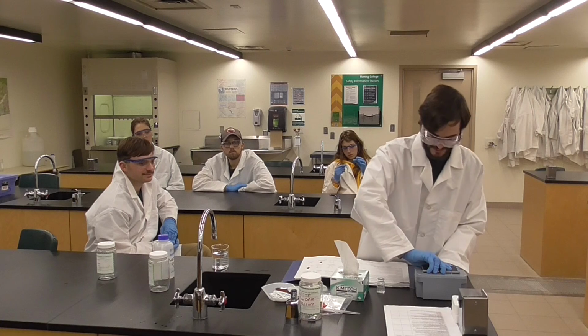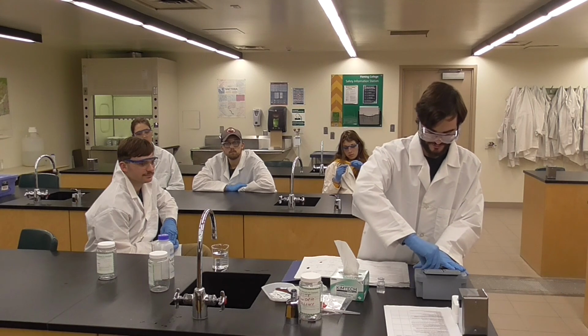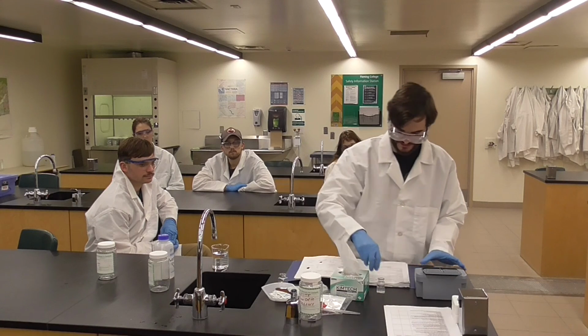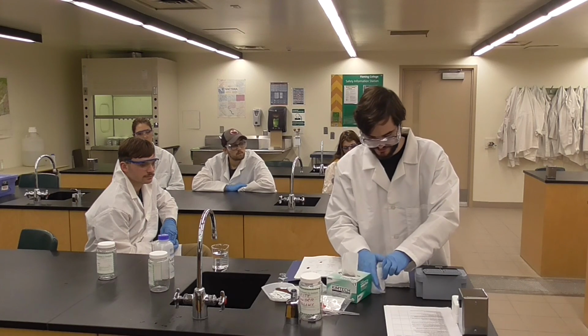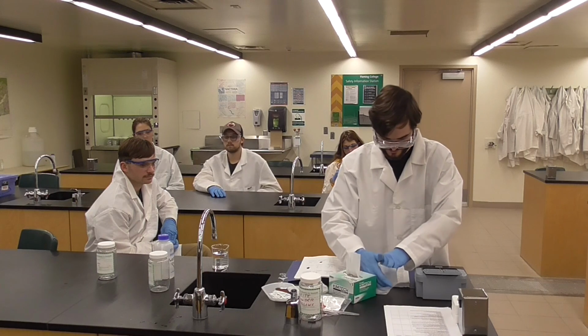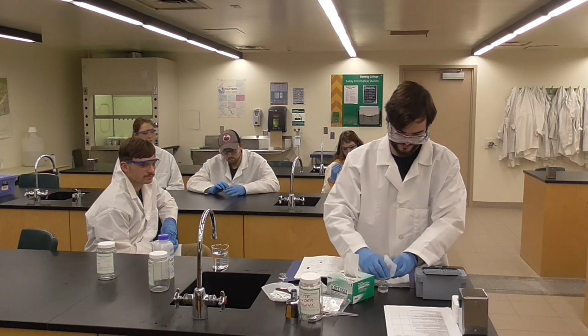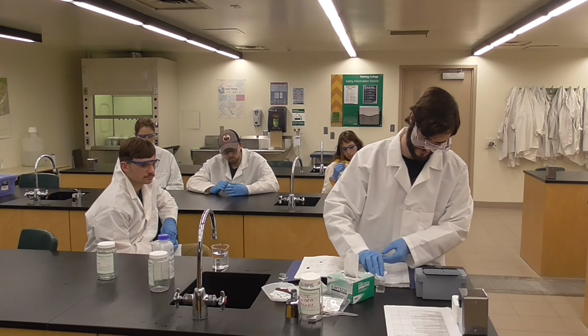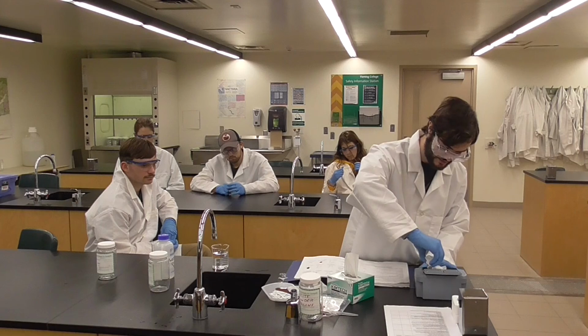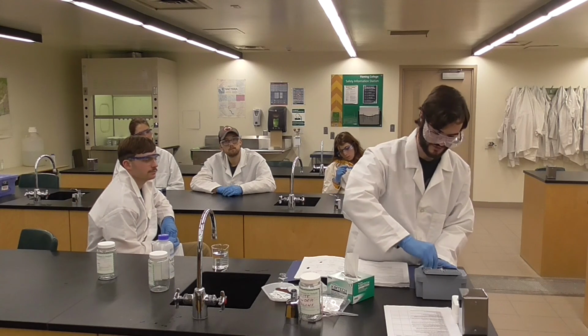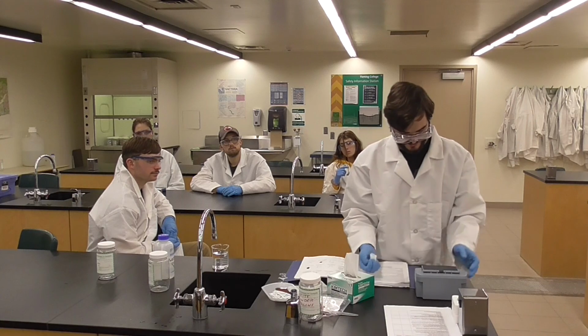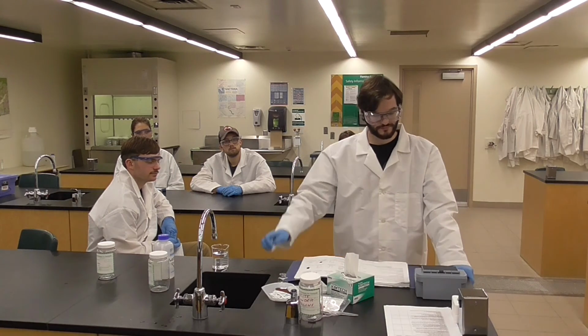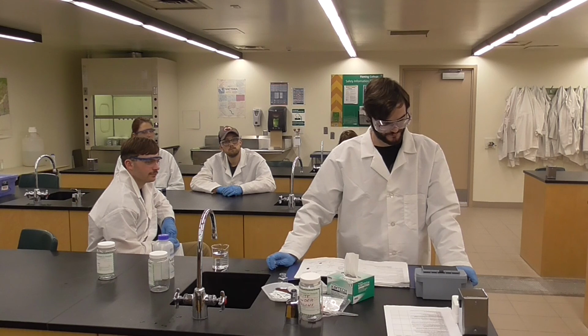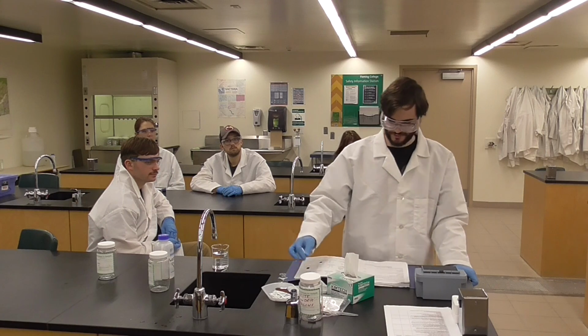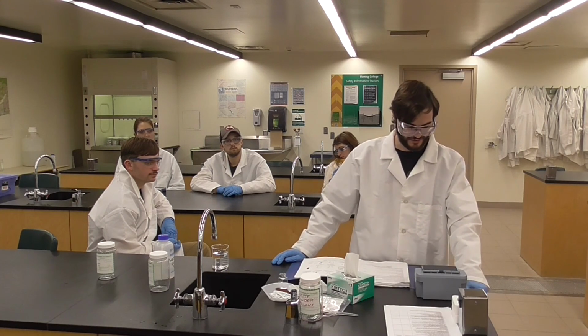So now it's reading 0 milligrams per liter of sulfate. Now we can remove our blank and take our sample cell and clean that off with the Kimwipe as well. And then once again with the fill line to the right, you can put it inside the spectrophotometer. Make sure the lid is closed and just hit read. There we go, so we have a reading of 14 milligrams per liter of sulfate.